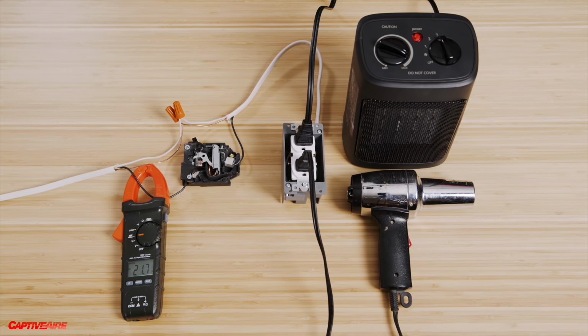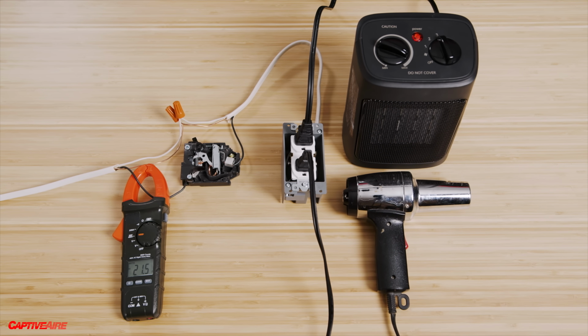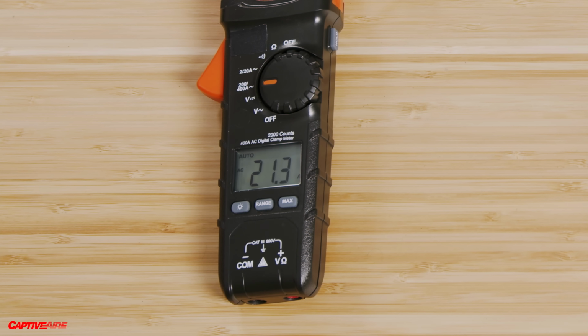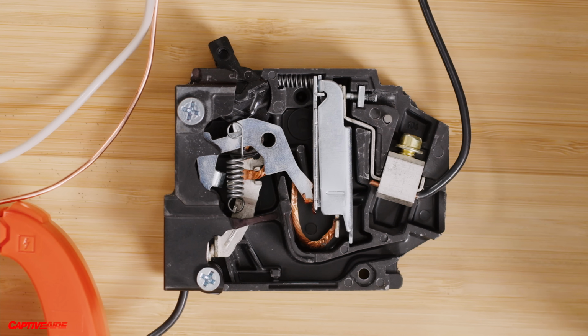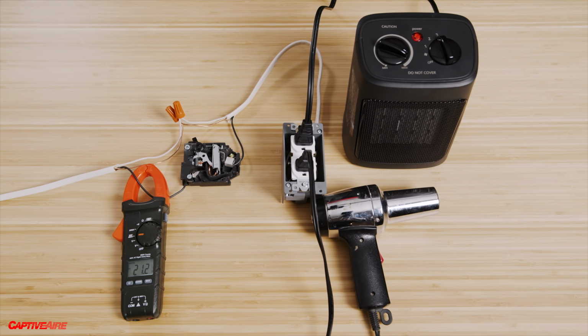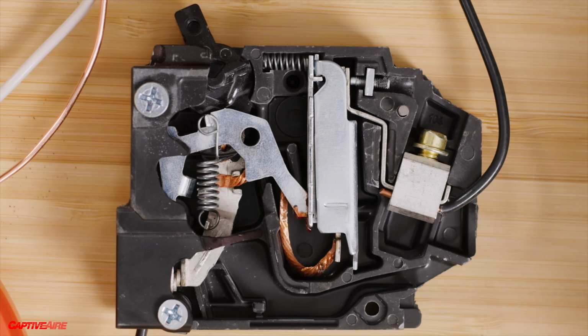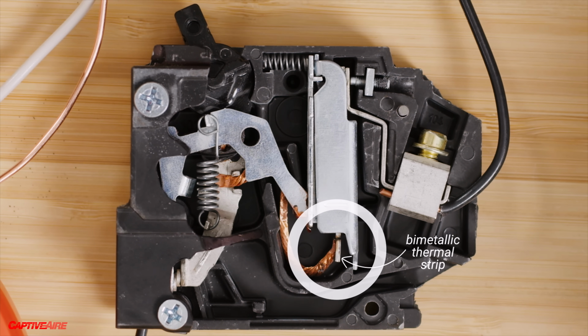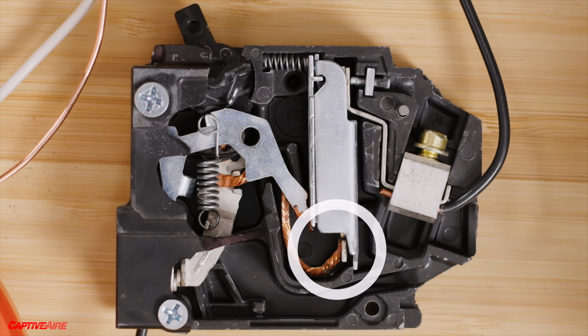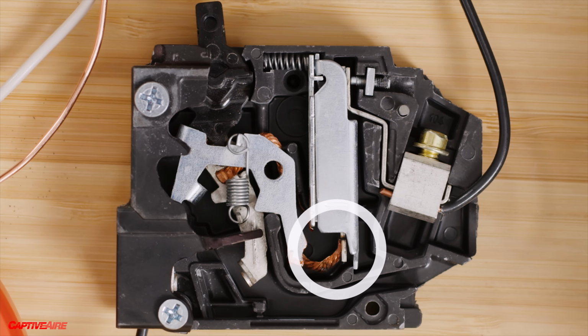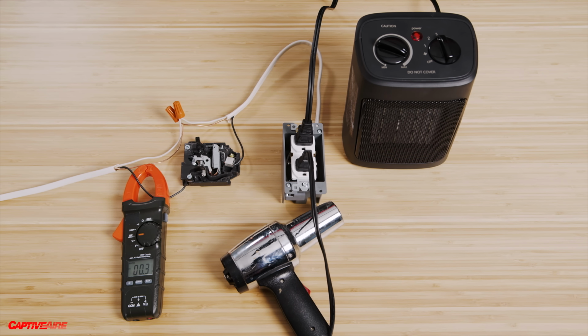In this setup, we have a space heater and a heat gun, and together they draw just over 21 amps. But you can see the circuit breaker is not tripping yet. As time goes on, the wires carrying this current are definitely heating up, but so is a tuned thermal element inside the circuit breaker. Here you can see it slowly moves as it expands. Eventually, this movement is enough to release a trip mechanism, which opens the circuit breaker and turns off the appliances, protecting the circuit from all that excess heat.